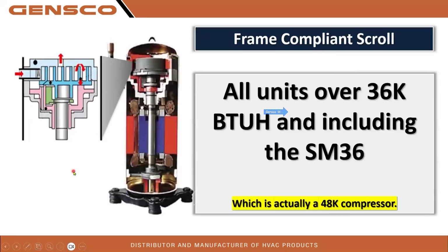The second compressor you may run into are the frame compliant scroll compressors. Every unit in the M&P world up to 36,000 BTUs will have the dual vane rotary compressor. Anything higher than that, a 42,000 PUZ, for instance, or any of the smart multi-units, and that includes the SM36, which is actually a 48K compressor. The exception to bigger than 36 would be the 5C42 ported type multi-zone unit, which is also a rotary compressor.